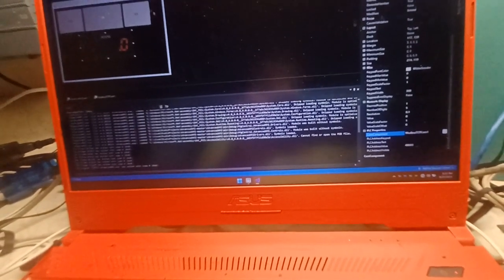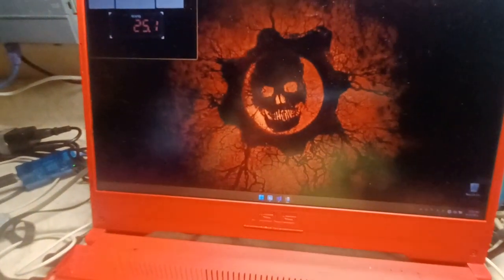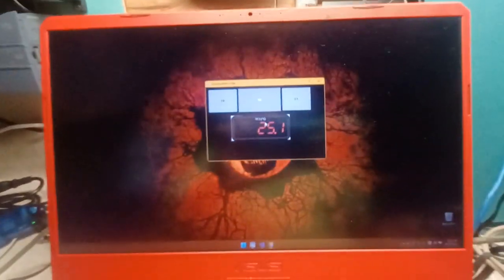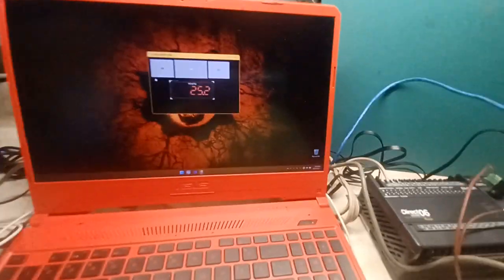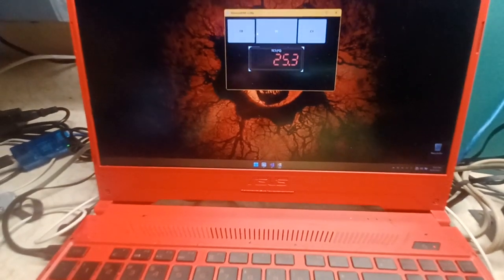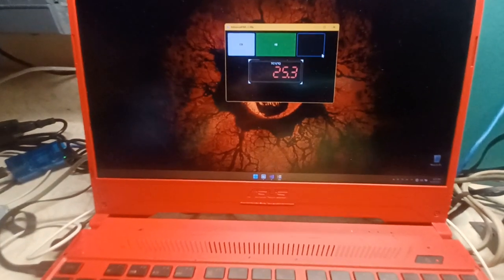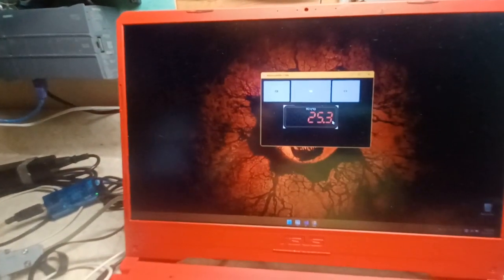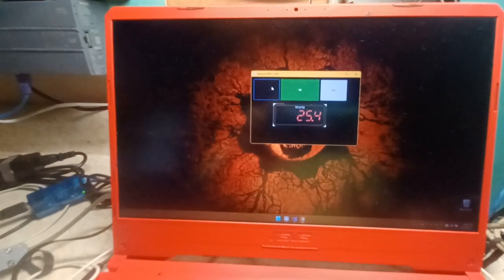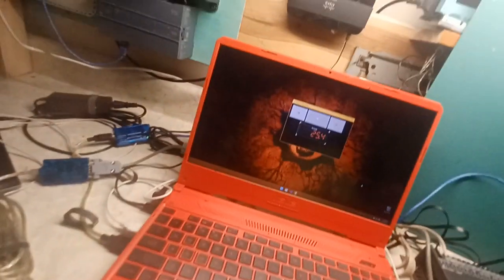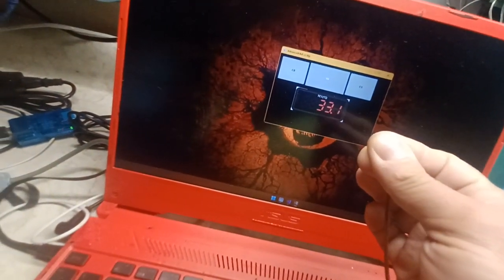And there is ModbusTCP. And then you run it. And you've got the same, right? But this is faster. I mean, I don't know if you guys can tell, but this is way faster than ModbusRTU. There's almost no lag, right? And it could go through wireless too. And I see temperature is also responding. The update is faster, so just wanted to show you that.